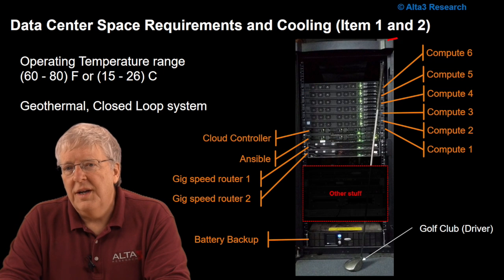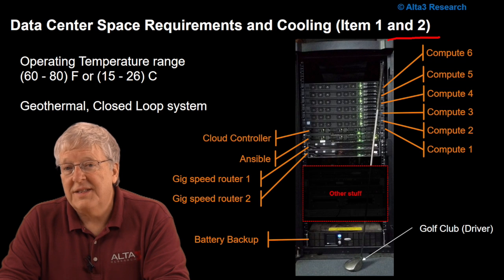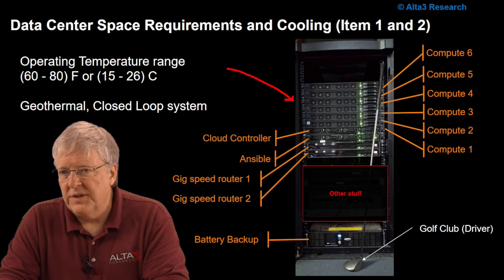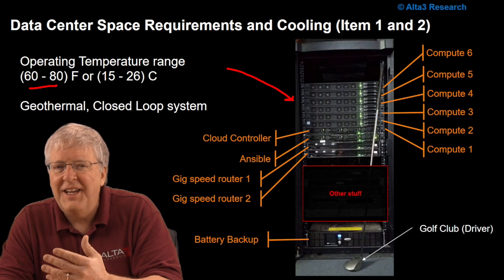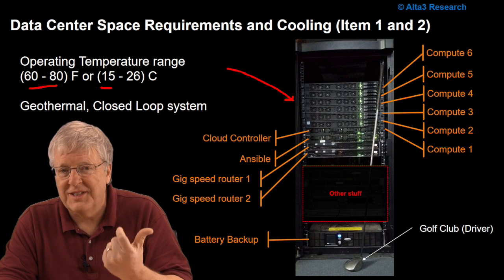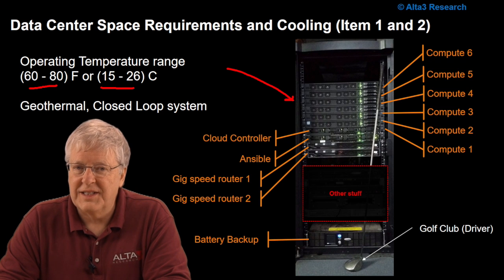Now, regarding item number 2, that's the actual cooling requirements. These are air-cooled servers that we're using. So in Fahrenheit, that would be 60 to 80 degrees, or in centigrade or Celsius, 15 to 26 C.